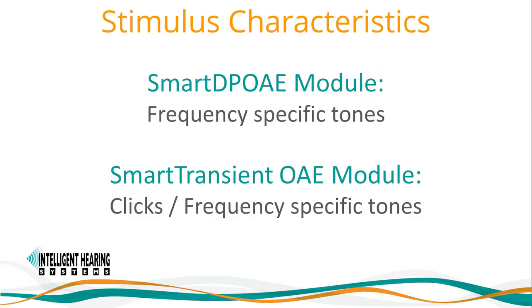There are primarily two types of stimuli used for clinical OAE testing. Distortion product OAEs are based on two frequency-specific tone stimulations, where the relationship between the frequency pair is typically F2 equals 1.22 times F1. In contrast, transient OAEs use a single short duration 75 microsecond click or a frequency-specific tone.